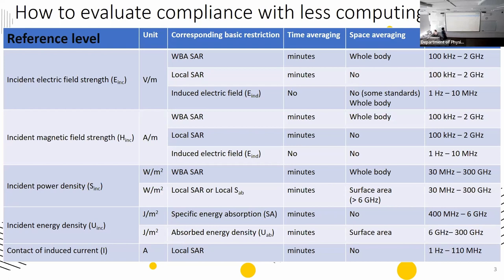Reference levels are much easier to calculate, but they are conservative because standards make conservative assumptions when deriving reference levels from basic restrictions. So if the power of your device is close to the limit, as in wireless power transfer, you may need to calculate the basic restrictions directly, even though it requires much more computation time and computing power.